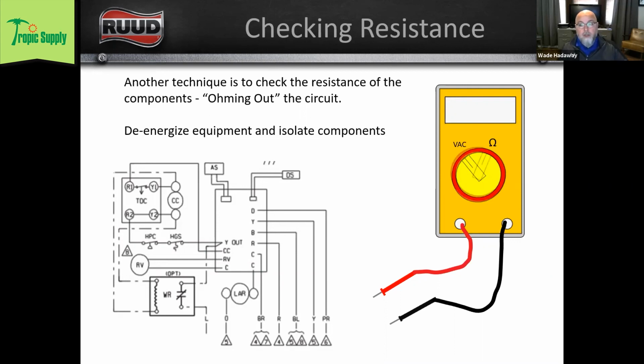First thing you're going to do is switch your meter to read resistance or ohms. A lot of people use a continuity setting for this, where if the switch is closed, the meter beeps. That's fine. You can use that setting as well.